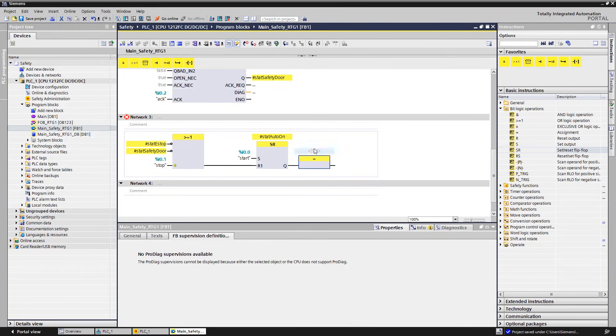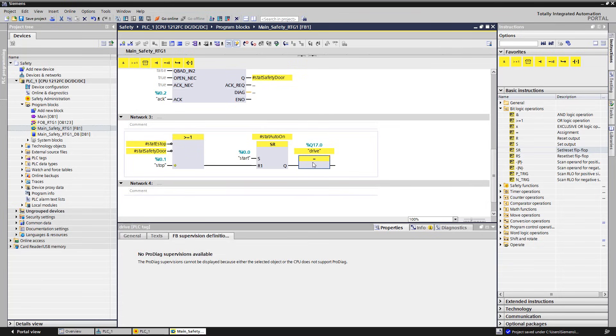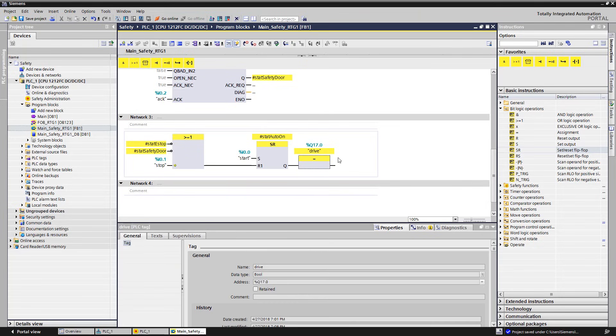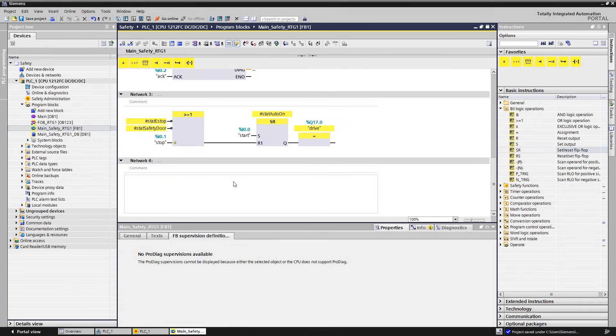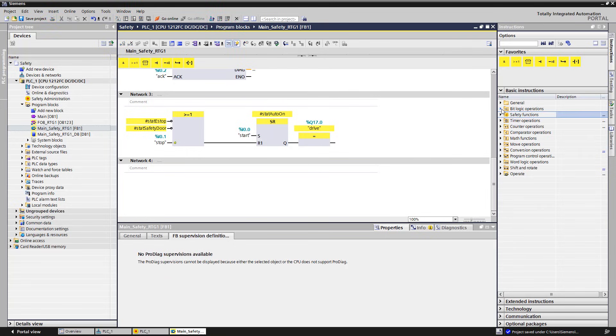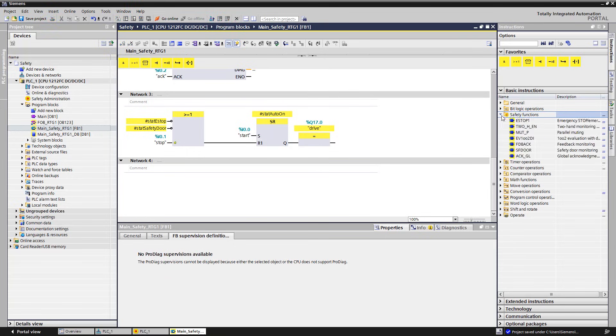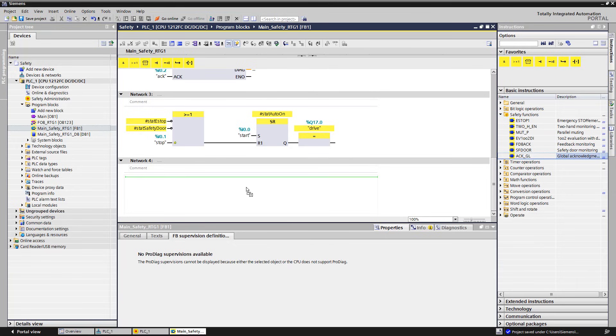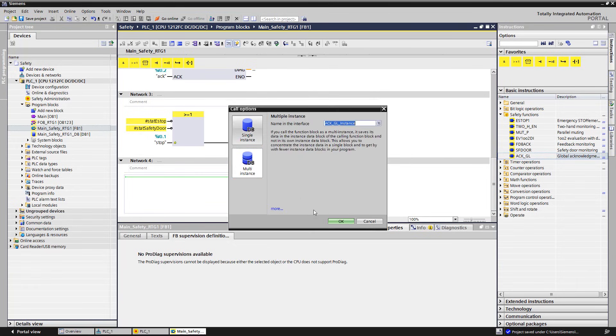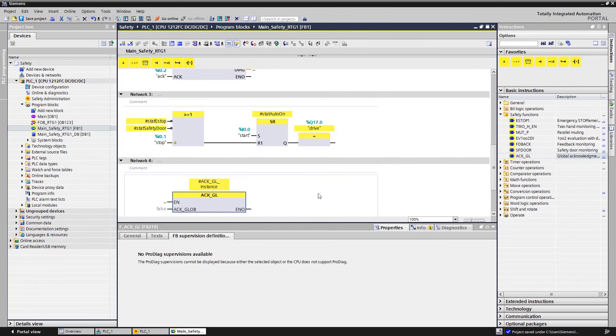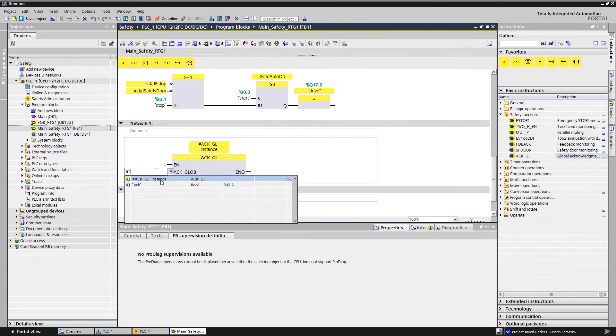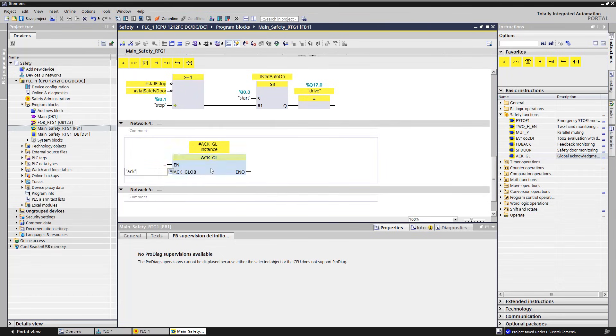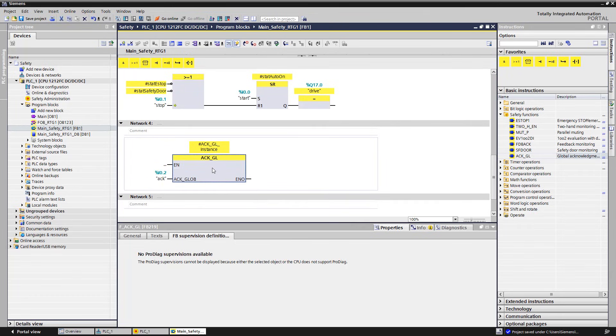The output drive is switched at this point via an assignment, but there is a special feature for the safety project planning. When a channel, module, or communication error occurs during operation, it is safely switched off and the affected module is passivated. The global acknowledgement for all F-modules is performed via the module ACK-GL. Only the acknowledgement button is connected with the ACK.